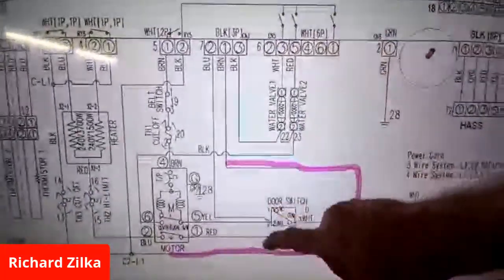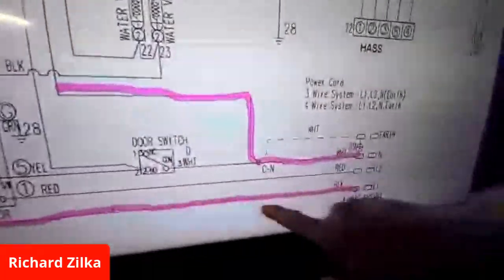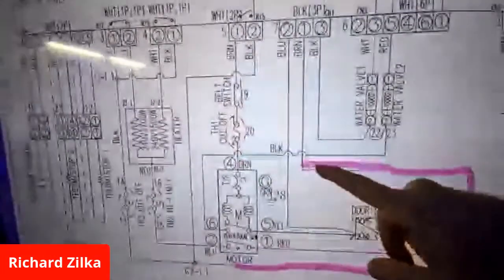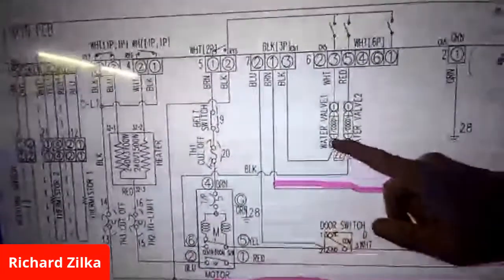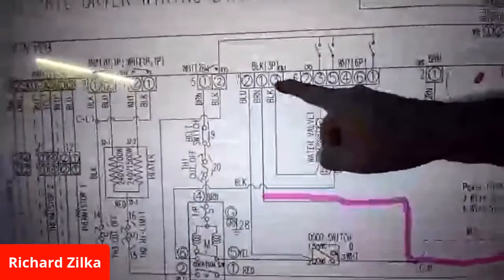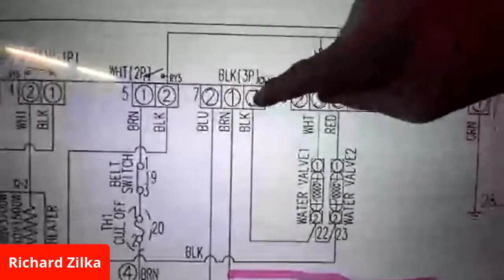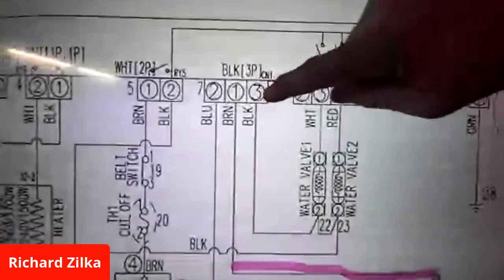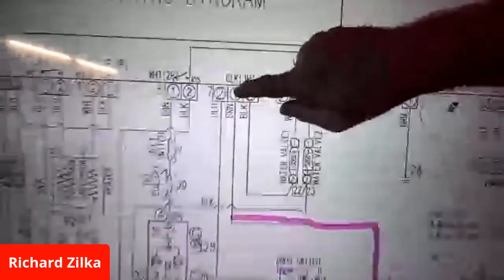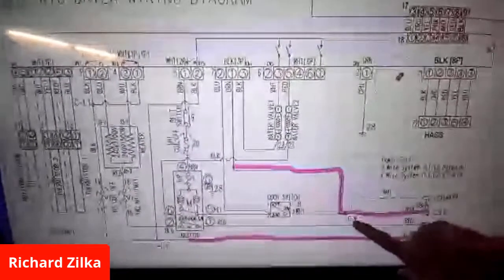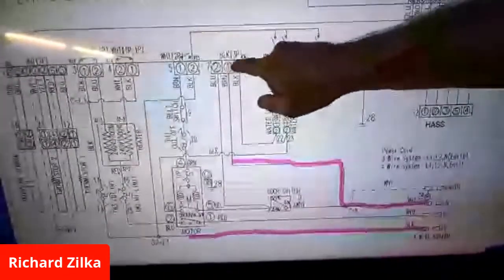And the black one coming in, let's follow that again. It comes over here, jumps, and goes to black here. So that's the incoming power, black and brown. Those two right there are line 1 and neutral. Even though it says brown, if we follow that brown back, it connects to the white over here. So we want to check that black and brown from that plug I just connected and see if we have 120 volts right there to feed that board.